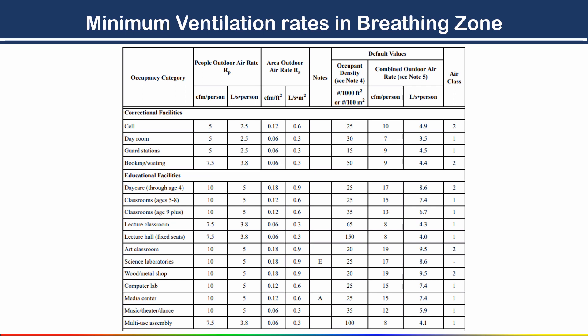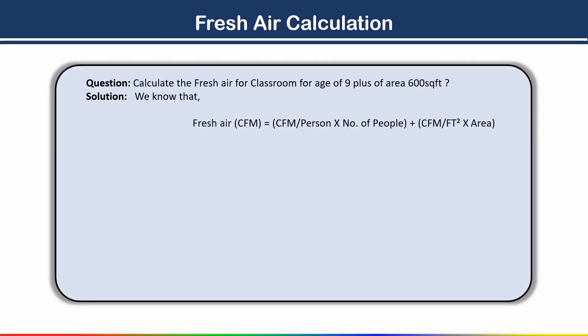In the ASHRAE ventilation standard, under the 'Minimum Ventilation Rate in Breathing Zone' table, you will find different options. The first column gives the occupancy category, then CFM per person value, then CFM per square feet value. For our question — classroom age 9 plus — the CFM per person value is 10, and the CFM per square feet value is 0.12.